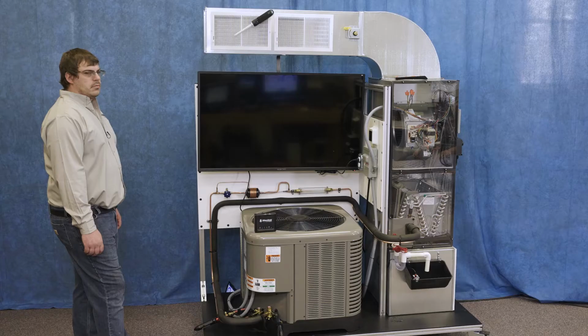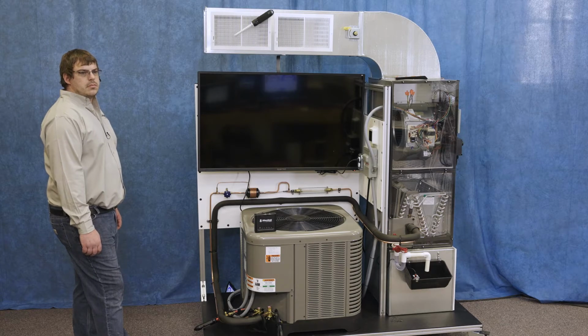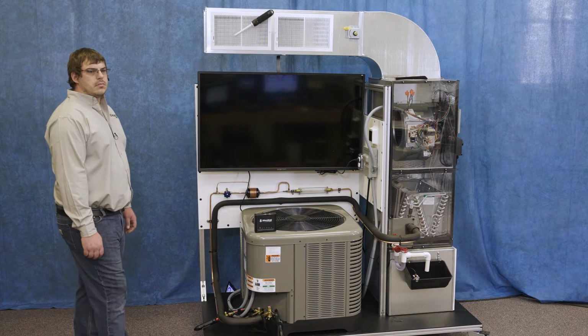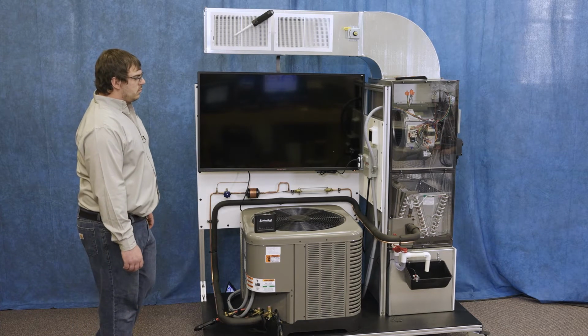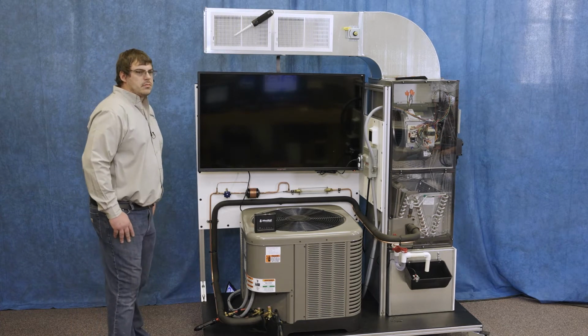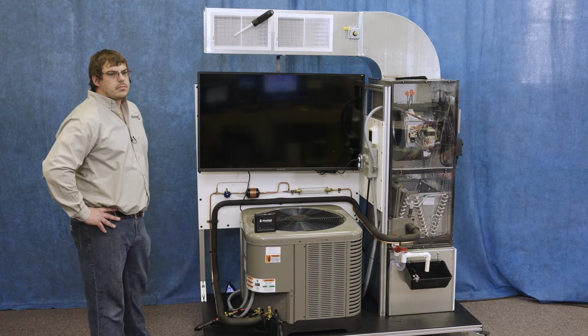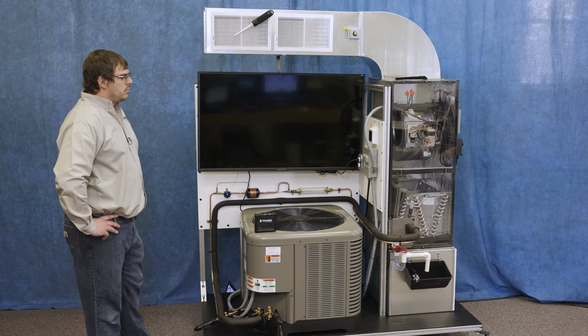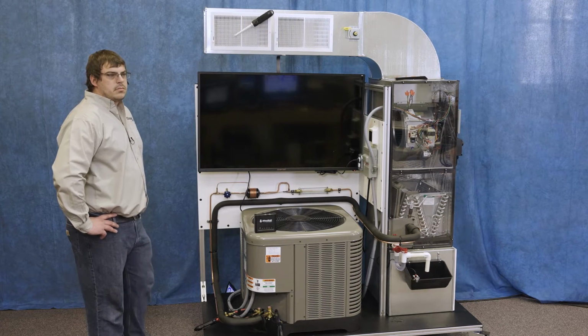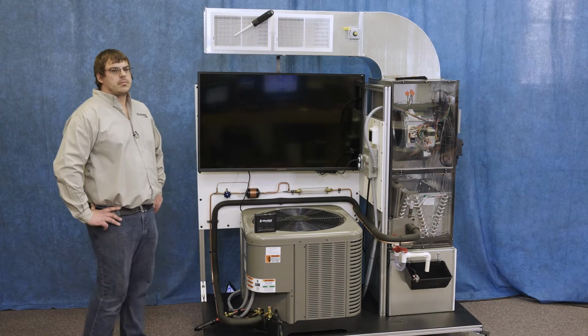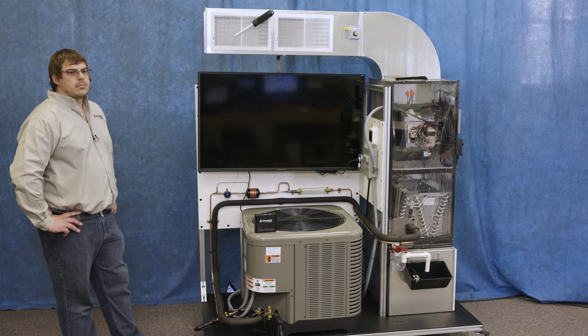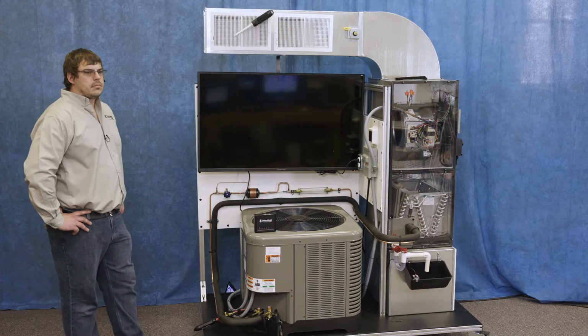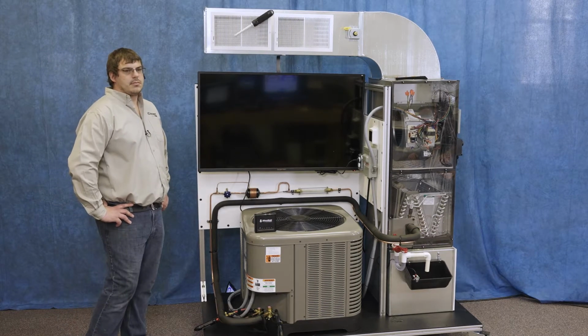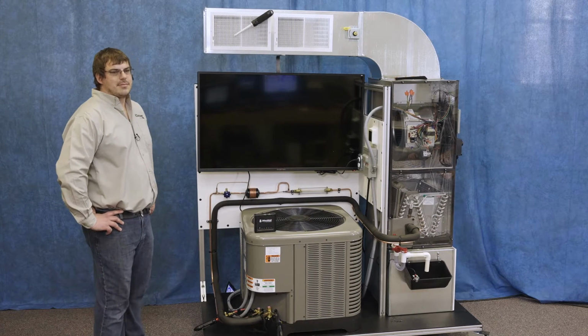And we've got our own EZ Trap there, which is a trap that is used constantly anytime a unit is above a conditioned space. We've also got a drain pan as well with an emergency float switch. All of these are critical for the student to understand that they are a necessity. We can use this trainer to show how to wire those in as well. A lot of times I will take those wires out and let the student wire those back in, and then we'll test it and see if it works. I always tell them that if they let the smoke out, it won't work anymore. So we always have to keep the smoke in the components.